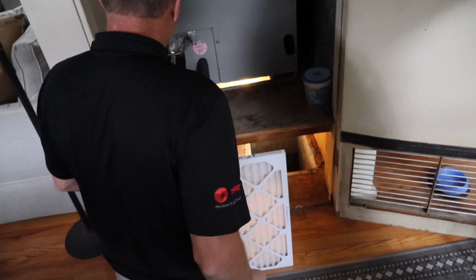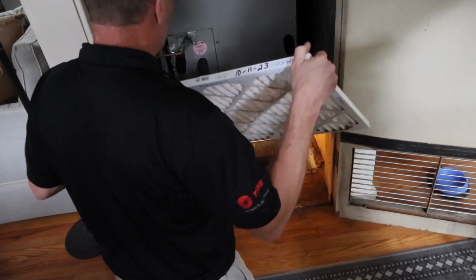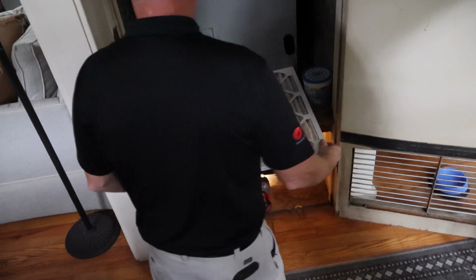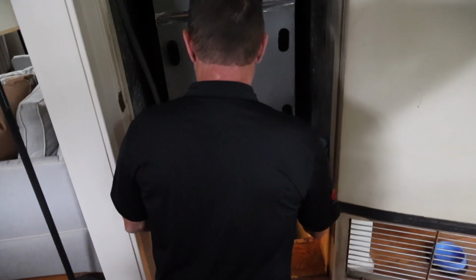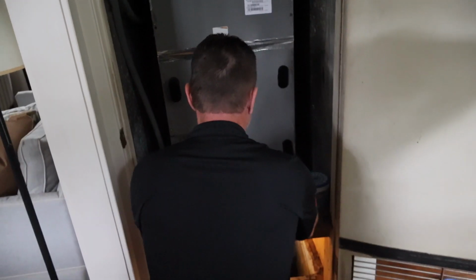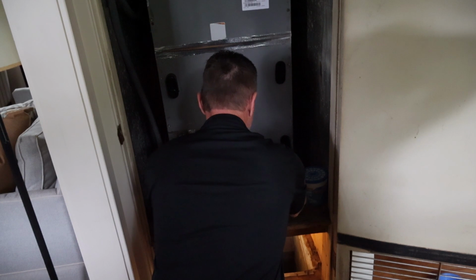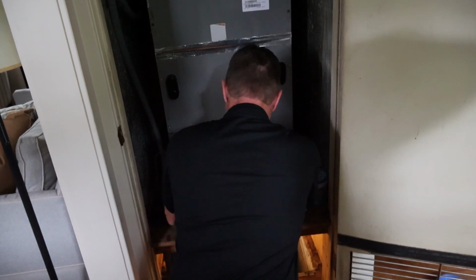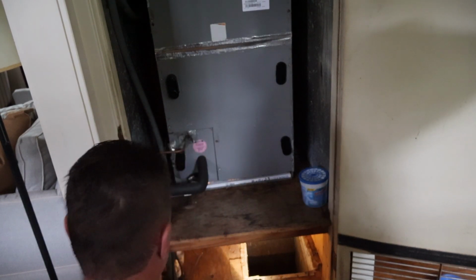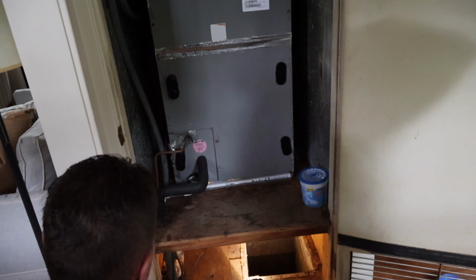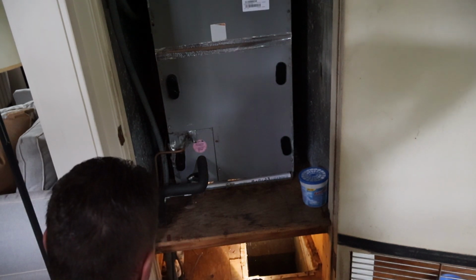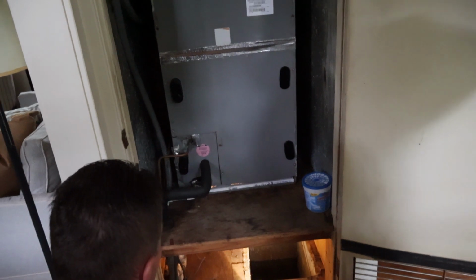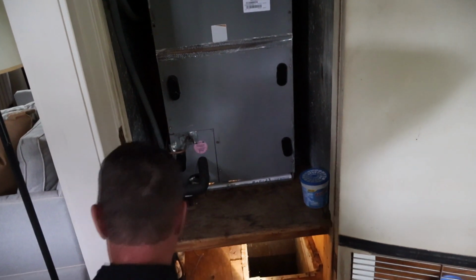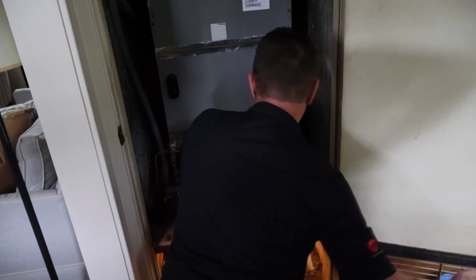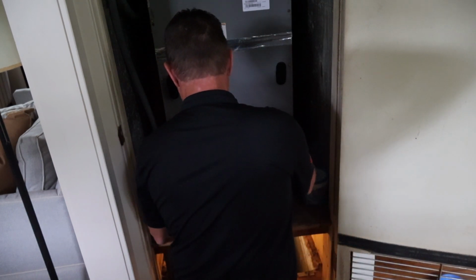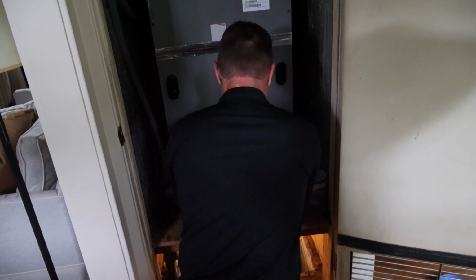Right, now we know when that filter has been changed, and so there's no question that we did do our job with the filter replacement. And it might not be a bad idea, now that we've slid the filter in, to take a glance at the coil while we're in that location. Already did it. He's already looked at it, and the coil does need to be cleaned. So we're going to make arrangements to have that coil cleaned at a later date.